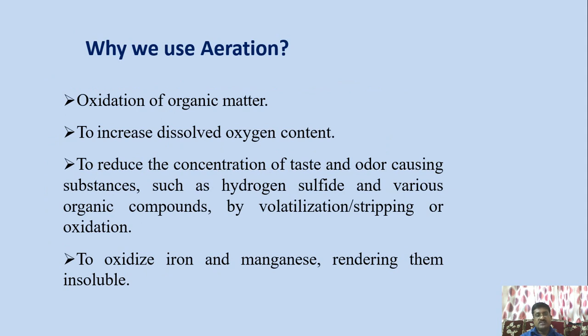The various functions for which we use aeration are: oxidation of organic matter, increasing the dissolved oxygen content, reducing the concentration of taste and odor causing substances such as hydrogen sulfide, and various organic compounds by volatilization, stripping or oxidation, and to oxidize iron and manganese rendering them insoluble.